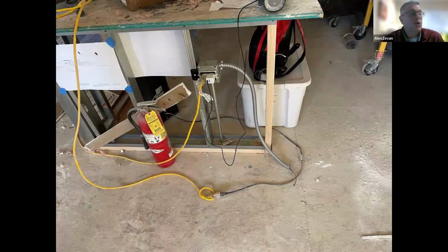Here's a good shot of an open gang box with not a properly tied knot there. As you can see, that could still be pulled apart. We have exposed wiring and we don't know if that's live or not. Even if someone tells us that it's turned off at the breaker, we don't know without testing. We want to make sure we're looking at all of this. We don't want tools or any type of metal contact going inside that gang box. Not a good situation here. We want to make sure that's not repeated.